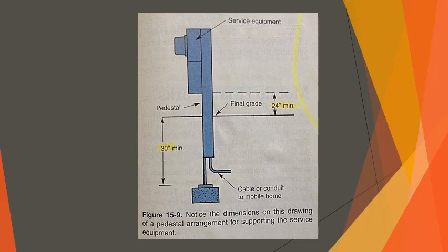The electric utility company usually installs the necessary service drop and transformer. The customer must supply the service pole and its components, as well as the meter pedestal for underground supply. Both pole and pedestal are permanent installations. The pedestal must be rigidly mounted so that it cannot be easily knocked over. Figure 15-9 illustrates a typical pedestal or pedestal arrangement.